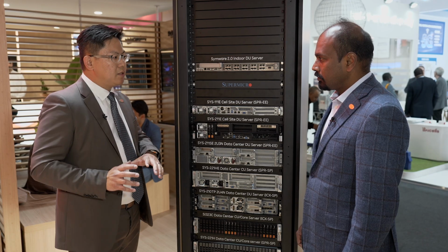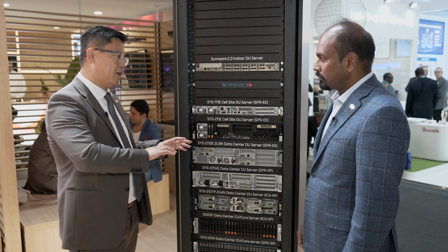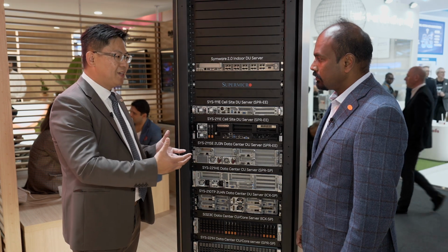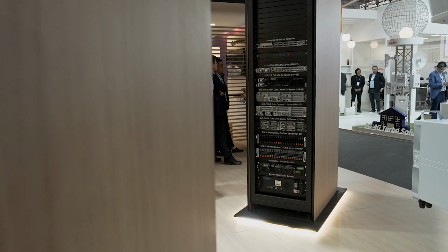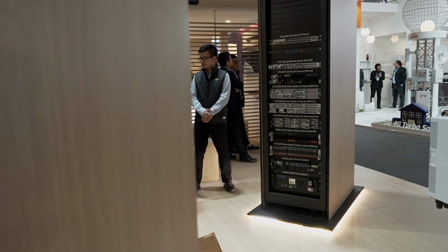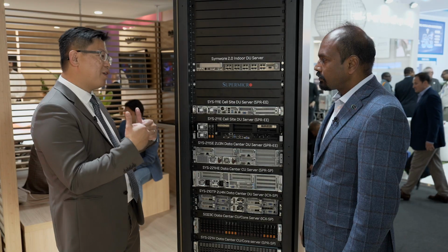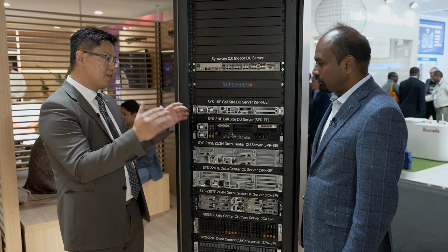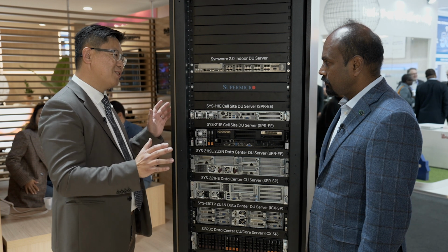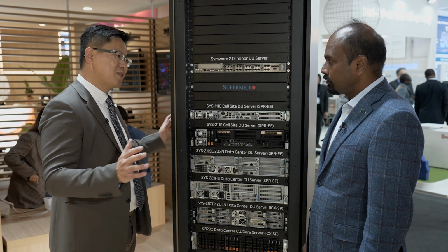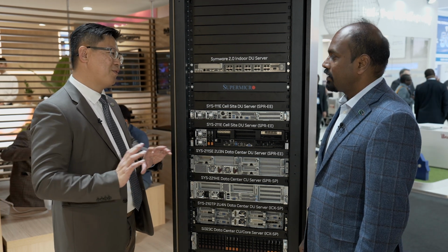When we move the data center technology to the edge, the requirements change. It no longer stays in the data center environment. The first big challenge is the cabinet size. The second thing is that things become front access because there's not enough space, so it's easier for maintenance. In the data center you have a cold zone and hot zone, but in the cabinet there's no zone, everything's at the front. So we have to change a little bit there.